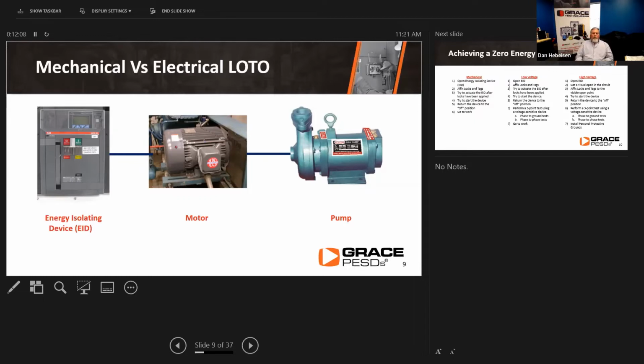And the delineation here between a mechanical lockout tagout and an electrical is we're not going to open up the motor cover. We're not going to engage with the wiring. We're not going to touch anything. We're simply there to tighten up a mechanical connection basically at the base of the motor, and then continue the work. So if we're going to actually touch conductors or rewire, then it becomes an electrical lockout tagout. If we're just doing something on the mechanical side, obviously it's going to stay as mechanical lockout tagout.